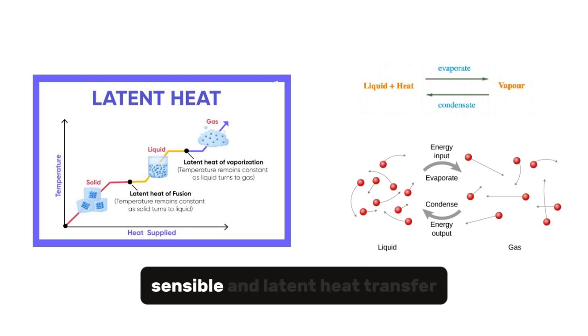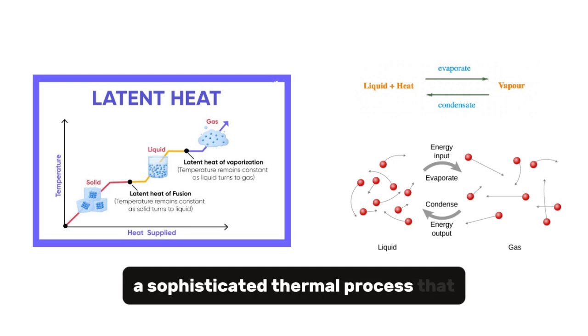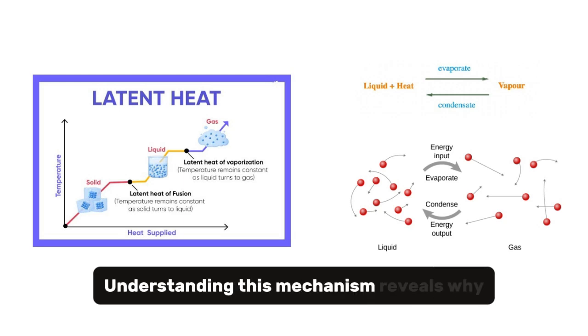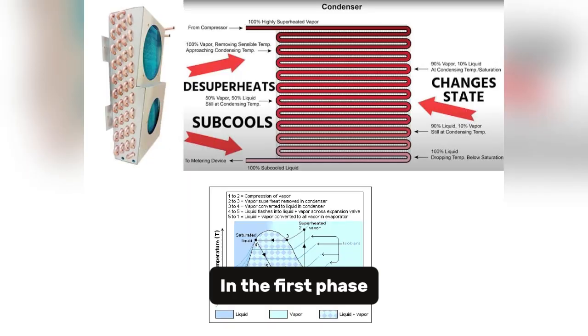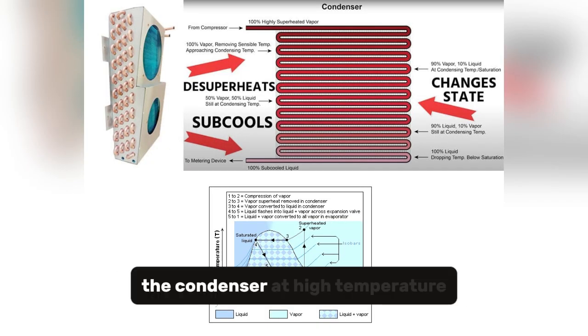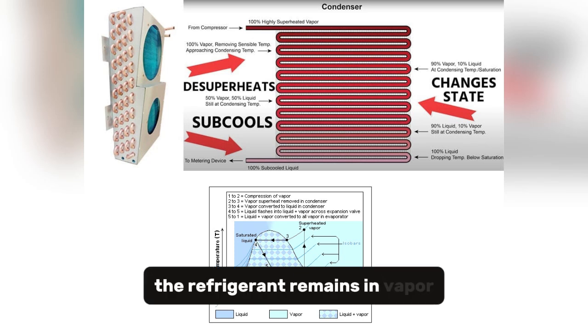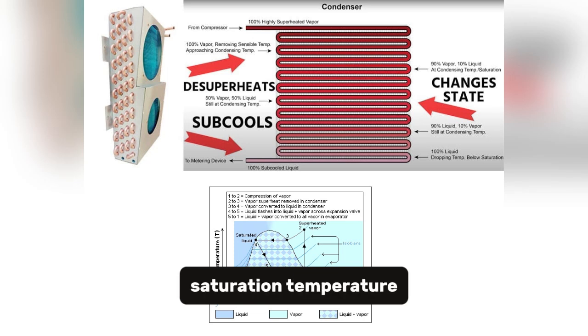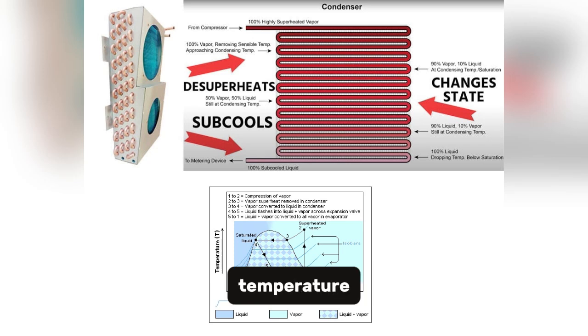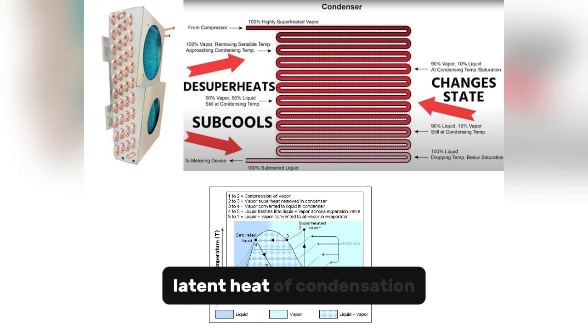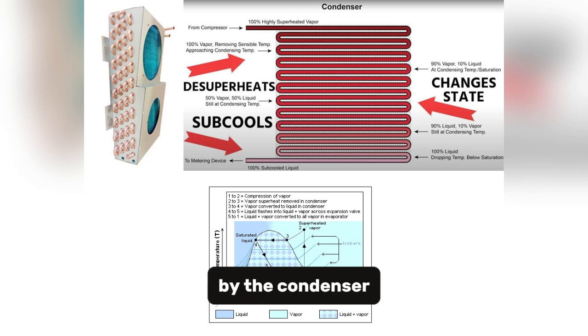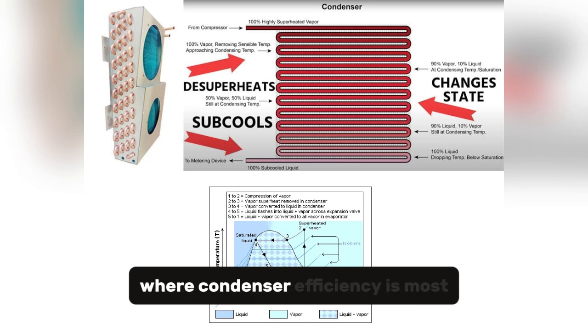The condenser's operation involves both sensible and latent heat transfer, a sophisticated thermal process that occurs in 3 distinct phases. Understanding this mechanism reveals why condenser design is so critical to system efficiency. In the first phase, superheated refrigerant vapor enters the condenser at high temperature and pressure from the compressor. Initially, the condenser removes sensible heat, cooling the vapor from its superheated state to its saturation temperature. During this phase, the refrigerant remains in vapor form, but its temperature drops significantly. The second phase involves the actual condensation process, where latent heat removal occurs. As the refrigerant reaches its saturation temperature, it begins changing from vapor to liquid while maintaining constant temperature. This phase change releases enormous amounts of energy, the latent heat of condensation, which must be efficiently removed by the condenser. This is where the majority of heat rejection occurs and where condenser efficiency is most critical.